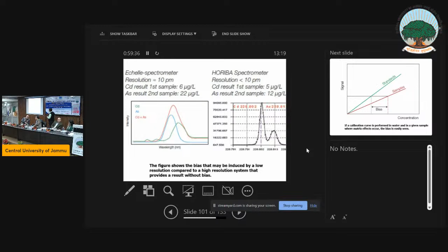That is the reason. Now you are choosing this. This instrument is not giving you this line. You are giving the number, which wavelength you want to have emission. So if you are giving some number and that coincides, you don't have the resolution power, and the other elements' emission lines will overlap with each other and give you 1 peak. They won't be able to resolve that. As the name is resolution power. So how to resolve adjacent lines will depend upon that. So this is your choice.